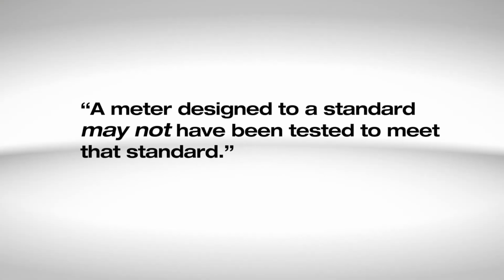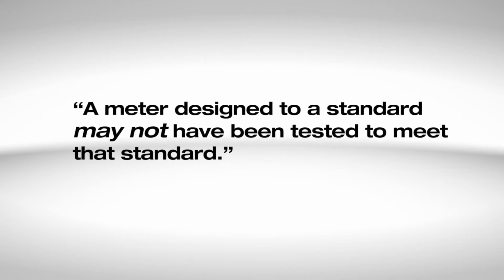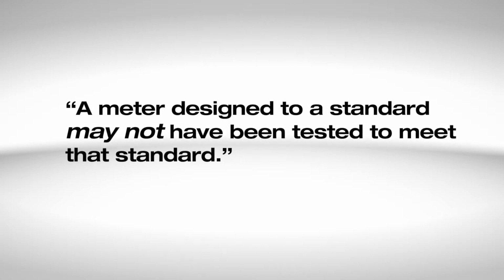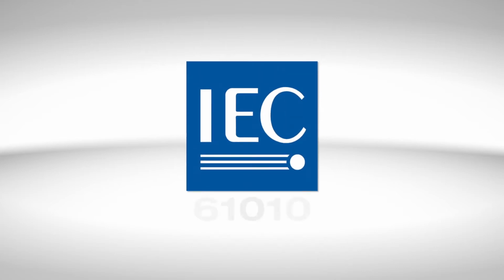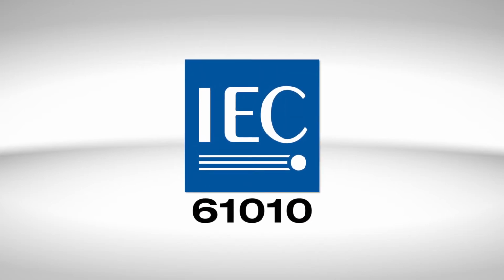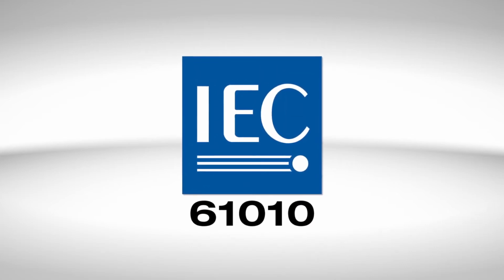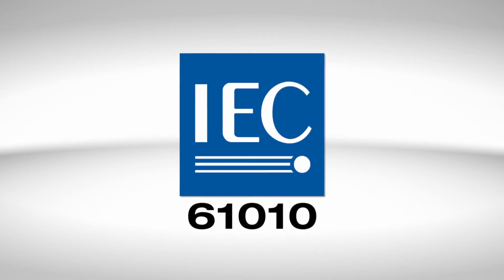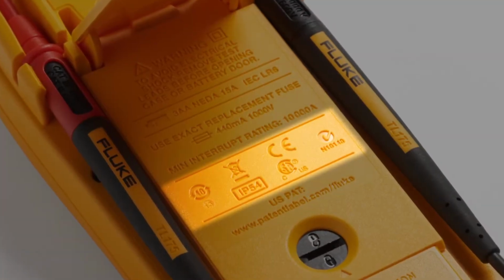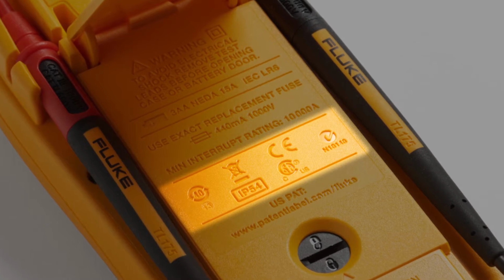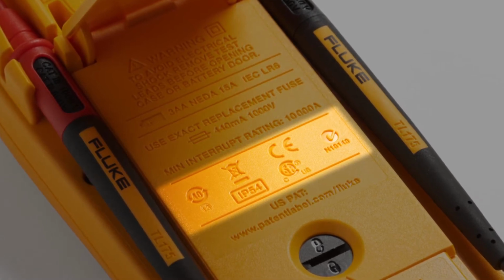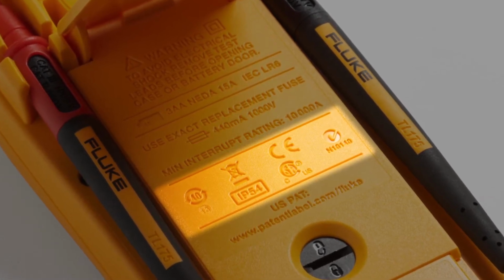It's important that test instruments and other electrical test tools are independently evaluated to make sure they can survive high voltage transients. It is essential to understand that standards bodies such as ANSI and IEC are not responsible for enforcing their standards. It is possible that some test instruments available today will not meet the IEC 61010 standard the manufacturer claims. That's why it's essential that the test instrument you use is labeled to show that it has been certified by at least one independent testing laboratory.